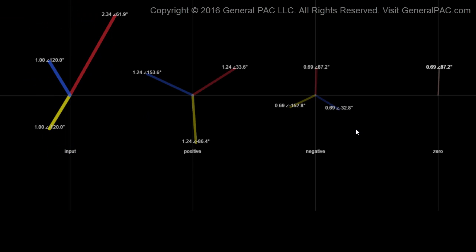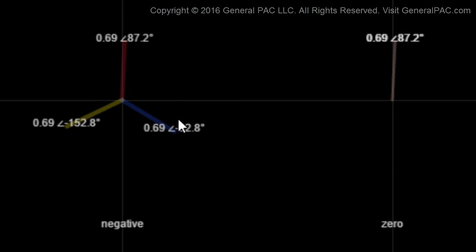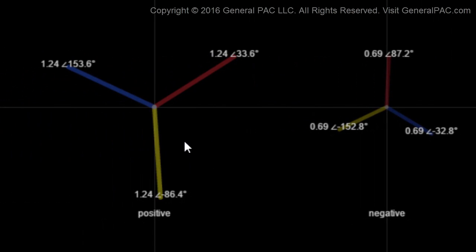Now let's separate these out and see how the sequence components look on their own axis. Our zero sequence components do in fact overlap each other, with this magnitude and this angle. Our negative sequence component — you can see it's a balanced system. The magnitude of the phasors are exactly the same, and the angle displacement between each phase is 120 degrees. So if you take this angle and subtract this angle, you get 120 degrees. We know that the negative sequence component is a balanced set, and our positive sequence component is also a balanced set, with all phasors having the same magnitude and displaced by 120 degrees.